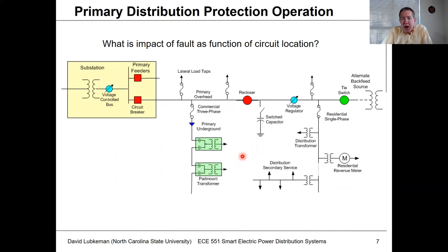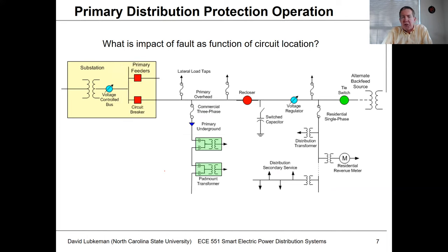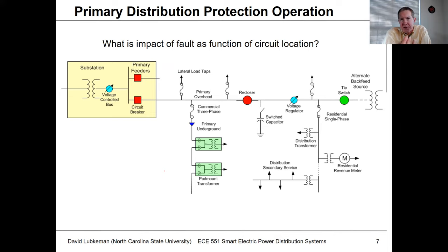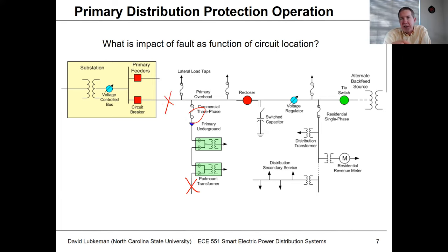Going back to the diagram we've been using for distribution circuits — primarily used for voltage regulation — here's what's going on as far as reliability and how it links to protection. You're going to have different sorts of faults that occur on circuits; it's just a fact of life. If we had a fault on this piece of cable right here, we'd expect the fuse to blow. If we had a fault on this overhead section coming out of the substation, we'd expect the circuit breaker to operate.